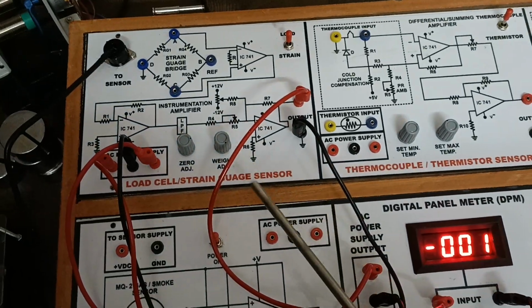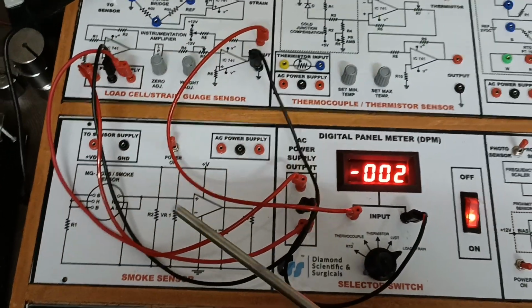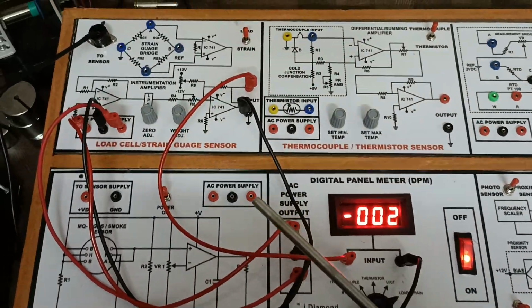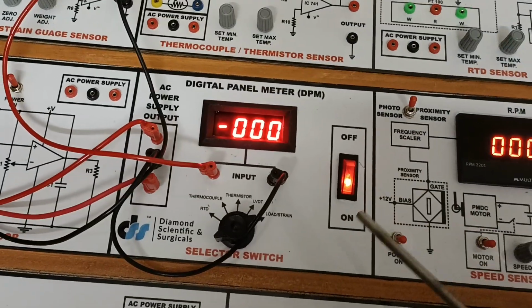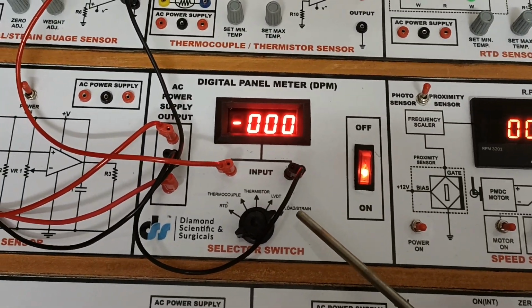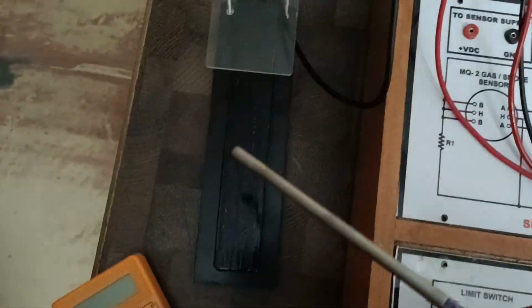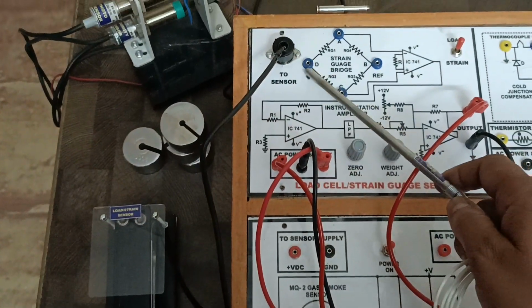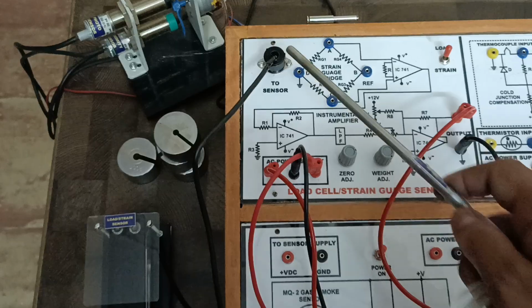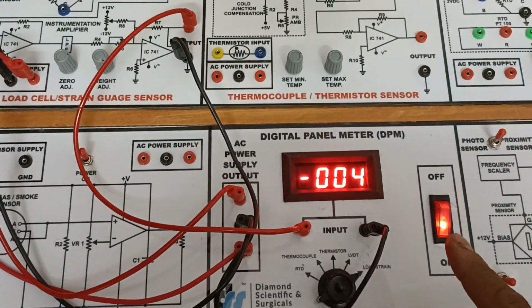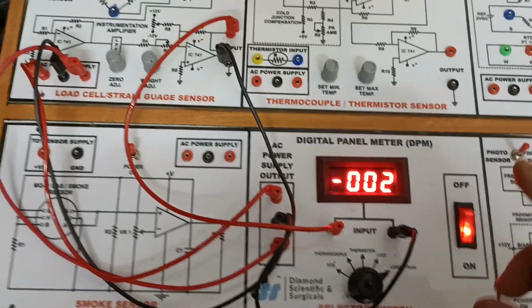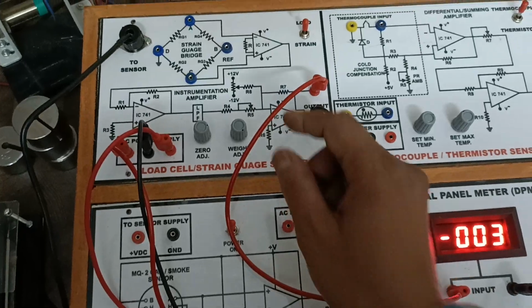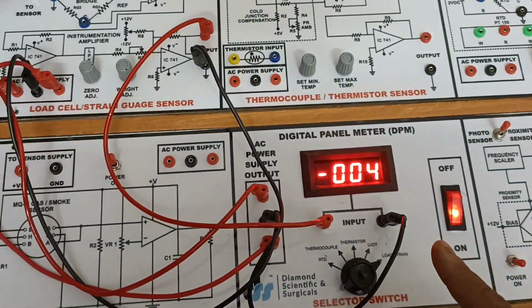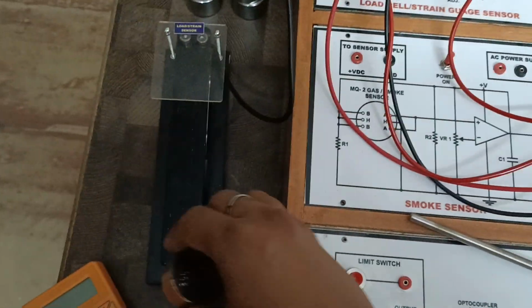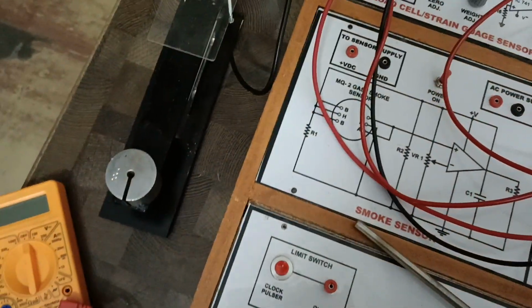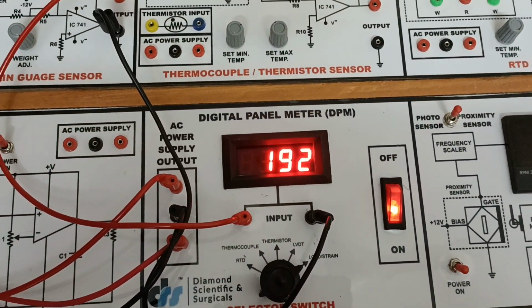First of all, we are going to demonstrate load cell upon strain sensor. In this sensor, we can connect the circuit as shown in the manual also, and then put the selector switch to load upon strain, and connect the load cell according to the wire. If the digital panel meter shows any reading, you can adjust the zero adjustment pot to show the zero reading, and then put the 200-gram weights on the load cell, and the meter shows some reading.